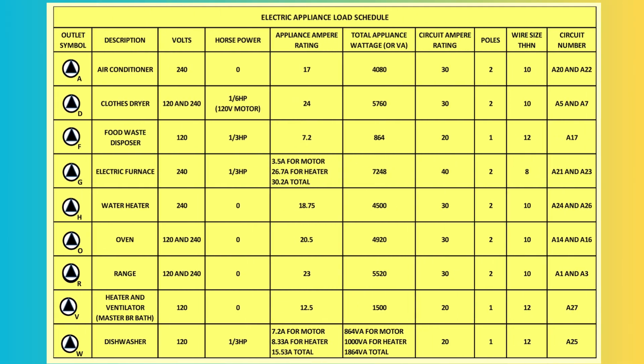The electrical appliance load schedule details the specific electrical loads of appliances and equipment. It includes circuit numbers that match with the electrical panel for correlation, descriptions specifying appliances or systems such as oven, refrigerator, air conditioner, and water heater, and voltage requirements indicating whether the appliance operates on 120V or 240V. Appliance load information includes ampere rating, wattage in volt amperes, and horsepower for motors and large equipment like air conditioners and dryers. Poles identify whether the circuit uses single-pole or double-pole breakers. The schedule is used for electrical load management, ensuring balanced distribution of power across circuits to prevent overloading, meeting electrical safety standards by correctly sizing breakers and wires, and providing a clear blueprint for troubleshooting or future upgrades.